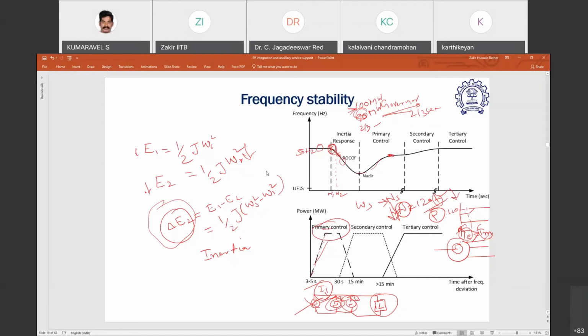Then comes the secondary control after the steady state value is actually achieved. Secondary control has two functions. Primary control has only one function. Primary role is to stabilize the frequency at the new steady state value. Secondary control has two responsibilities. One is it has to bring the frequency back to the nominal value or at least the pre-disturbance value. That is the first function of the secondary controller. Second responsibility of the secondary controller is to release the primary control reserve.